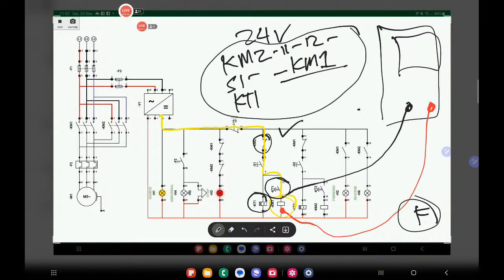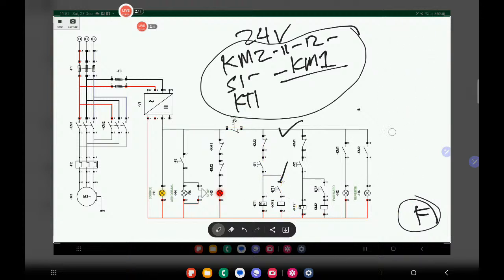So for me, it is much faster to troubleshoot this one, because how would you know if your KT1 is activating or not, or if this one is closing, if you're testing the system in a dead circuit? You switch off the main breaker, you don't know if your timer is counting or not. That is also one of the limitations when you are doing dead circuit troubleshooting. So I hope you're getting my point on why I'm saying that it is much faster to do live circuit testing when you are troubleshooting. It makes your troubleshooting easier, no?